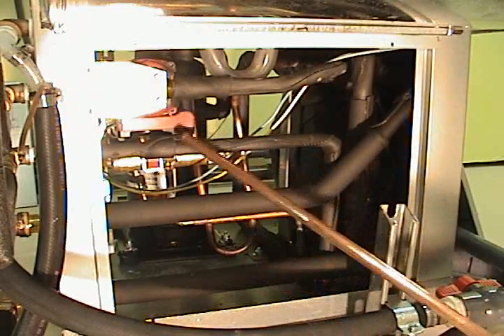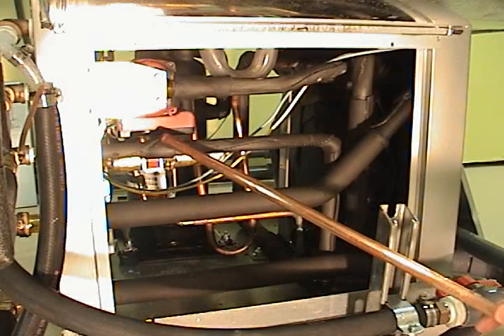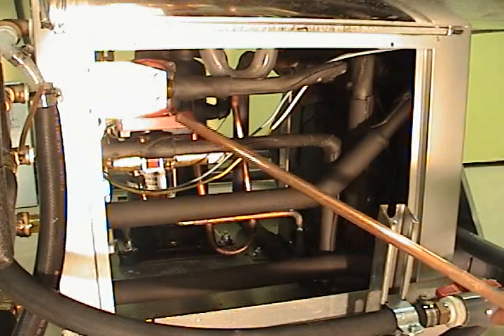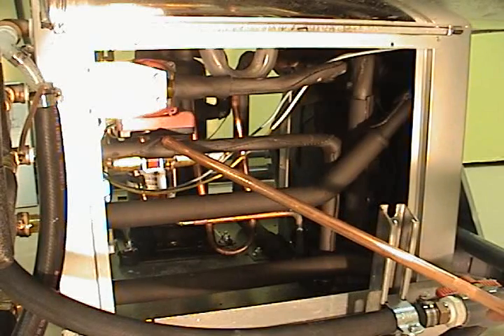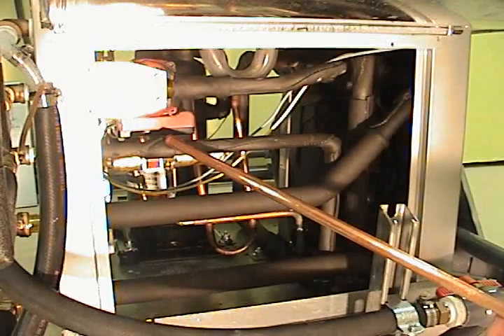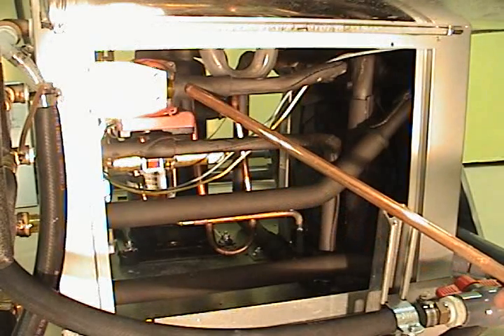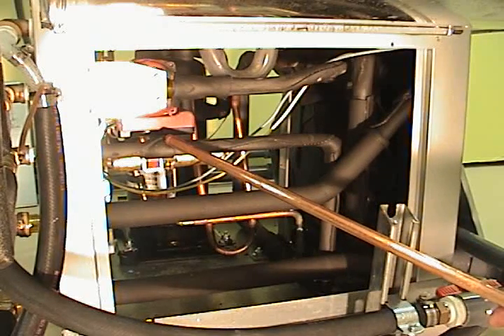Many units have a thermistor, or a temperature sensor, that will sense the temperature of the incoming water from the tank. When it reaches 125 degrees, it will turn the circulating pump off so it doesn't heat it further. This particular unit does not have that — it's not equipped with it.